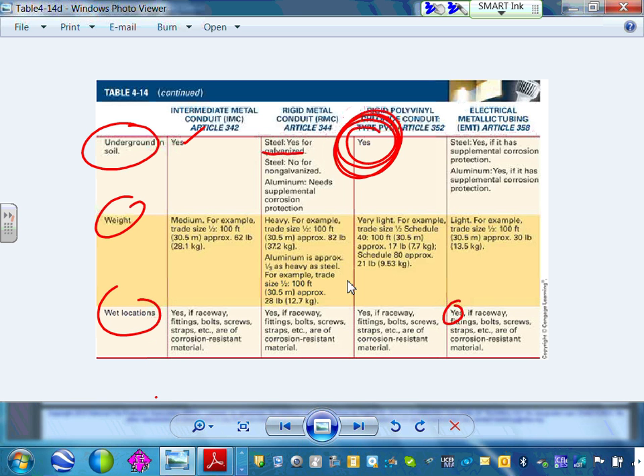Forklifts in the manufacturing floor - you guys are going to be touring a manufacturing floor, forklifts are running around all over, rigid. Gas stations, hazardous locations, flammable gases and liquids and dust - rigid. So these are really the only places where you don't use EMT.